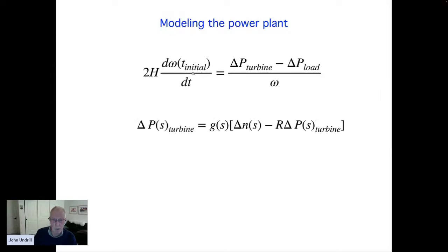The load assumes the privilege of turning on the light switch and having power delivered. It's not that the load sends an email to the generator and says, please make some more power. The load turns on and the generator is expected to respond. So we need to describe the power plant, which is the surrounding equipment around this rotating mass, by a transfer function.